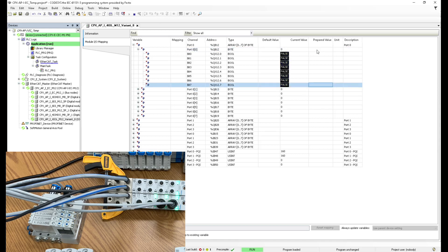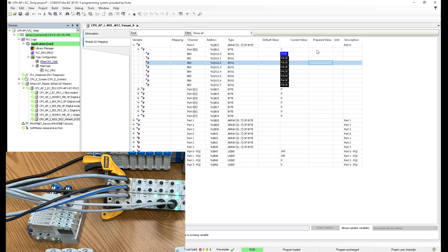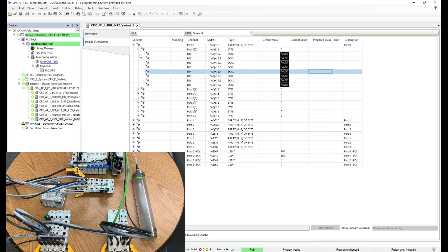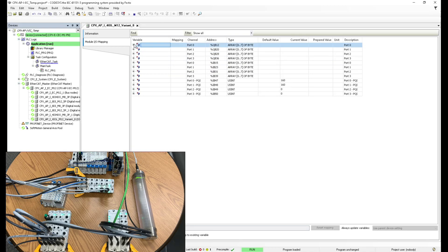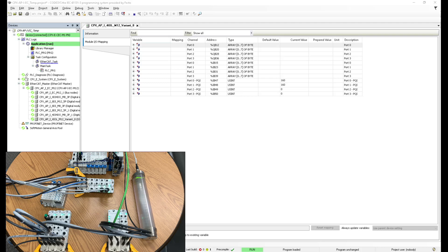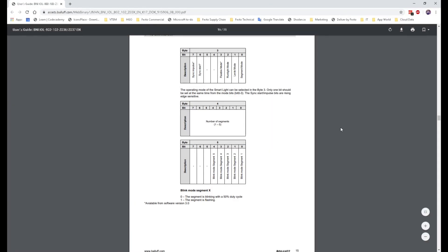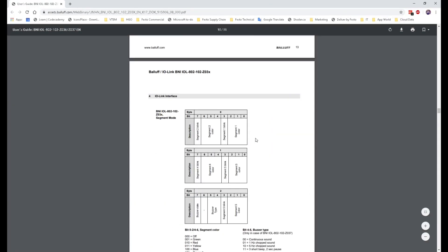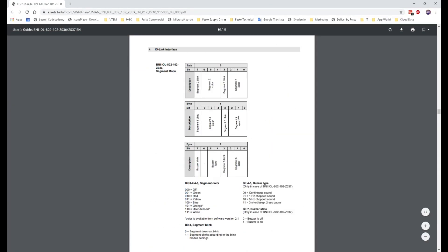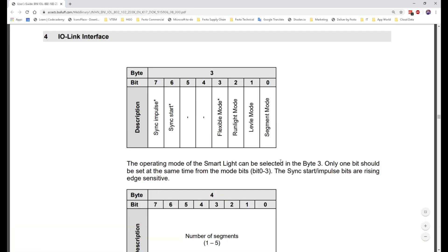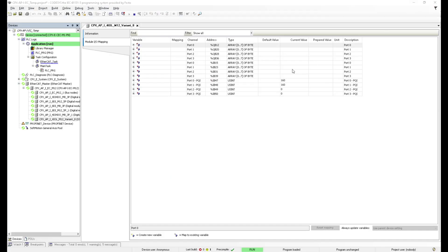And of course I could do coil by coil if I wanted to. Perfect. Now, same thing with that stack light. Let me just bring up that user manual. So if I go to the stack light data sheet, it says that if I switch on byte number three, there is a run light mode. Byte three, bit two. Let's do that. So that's connected on port one. Byte three. Byte three, bit two. If we switch this one on...